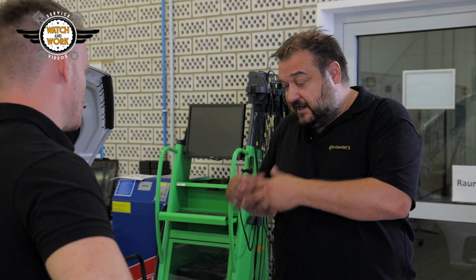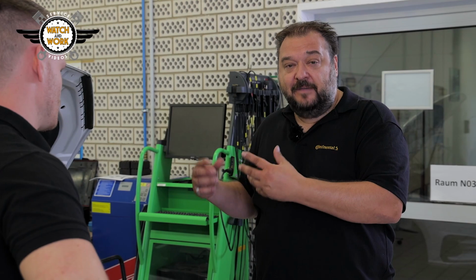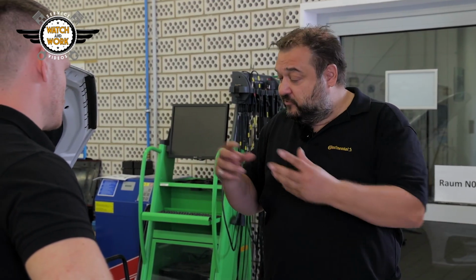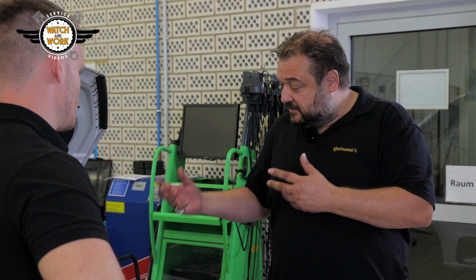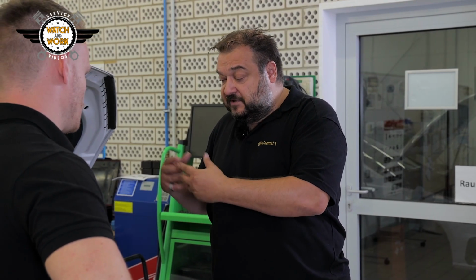Exactly. The surfaces are protected by additives in the coolant. If we remove an aluminum component from the system, such as the heat exchanger, then fit a new part, its surfaces will lack this protection and it can only be provided by fresh additives. Because we have a lifetime coolant fill here, the additives in it have already been distributed to all existing components. This means these additives are now missing from the old coolant, which is why we need to completely remove all the old sludge and refill the system with fresh new coolant.